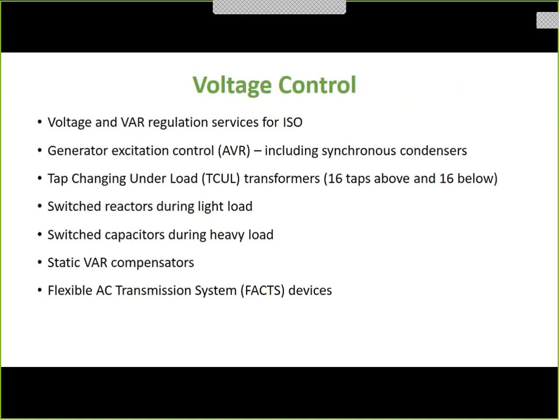Now, voltage control, there's a lot of other ways. There's generator excitation control. That's the one I just talked about. There's also tap changing under load transformers. The taps change to give you higher voltage or lower voltage. There's switched reactors. Light load, you switch a reactor in because you lost all the industry. At heavy load, you want capacitors instead. And there's a thing called static VAR compensators, which are just like capacitors and inductors. And there's FACTS, flexible AC transmission system. These are big power electronics. We're talking thousands of volts, thousands of amps going through transistors. It's big power electronics.